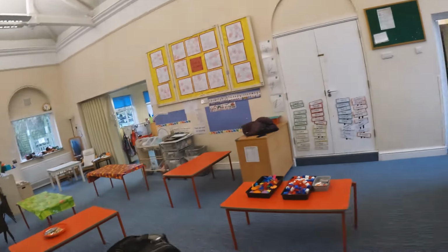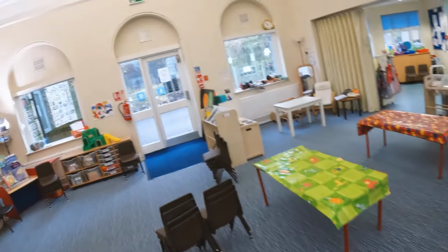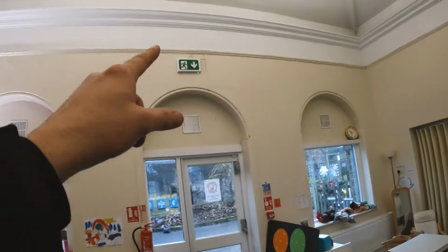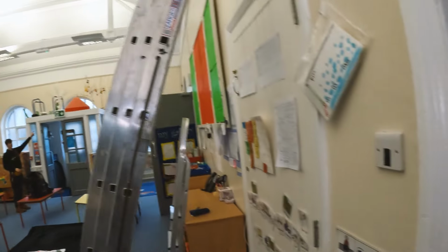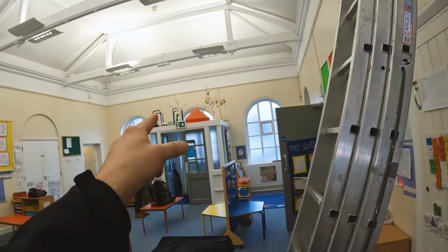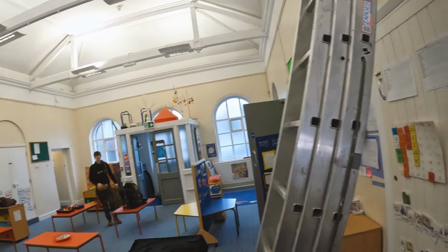Right, Alice has just turned that on, so let's make sure the lights are on then. So note what emergency lights are on. This one's on, so we can ignore that. But a cable went out and went somewhere, didn't it? That one there? But it could go into that and then off somewhere else, so we need to have a good look around. There we go, this is on. That's on, and then, what, you've got one off over here? So that's off, is it? Yeah. Right, so we've got one emergency light off there. If that's it, we'll look into that, but we'll need to look everywhere.